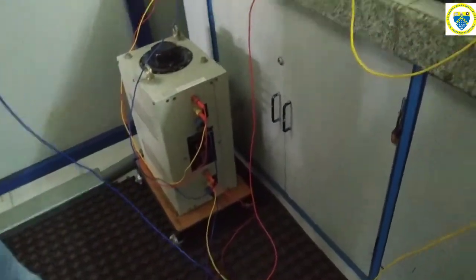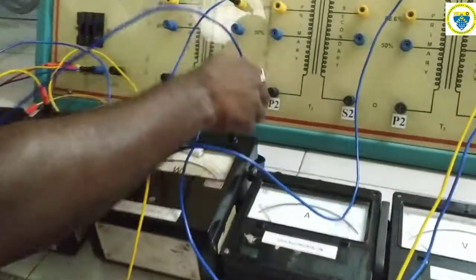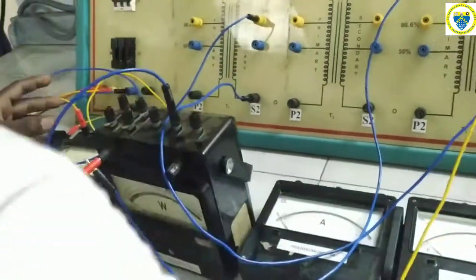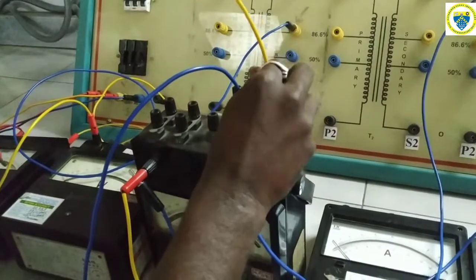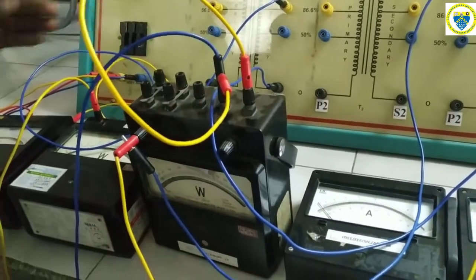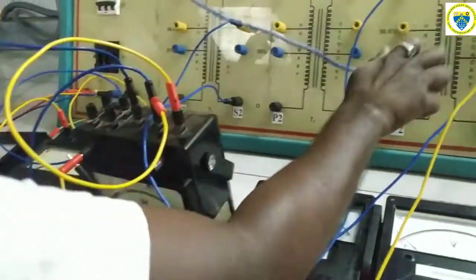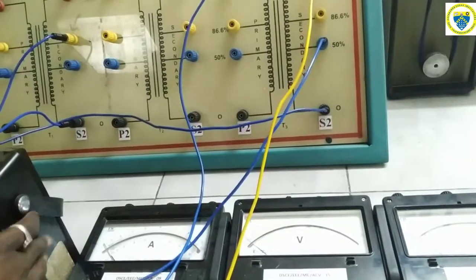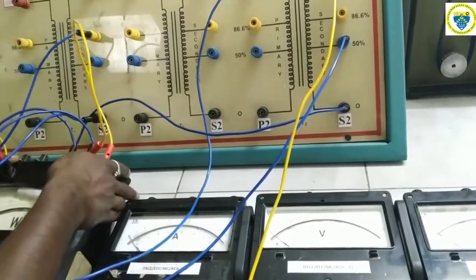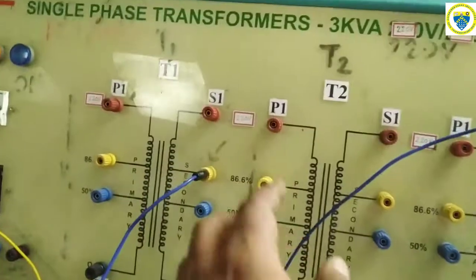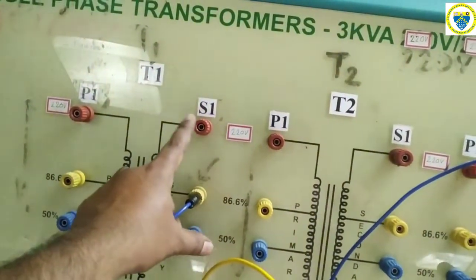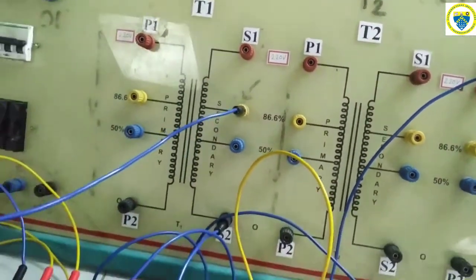And next from B phase of the auto transformer. B phase of the auto transformer should be given to the M terminal of wattmeter 2. Again MC should be shorted. Again the L terminal of wattmeter 2 should go to S2 of the teaser transformer, and here the S1 terminal of the main transformer should be open, so we should take note of it.